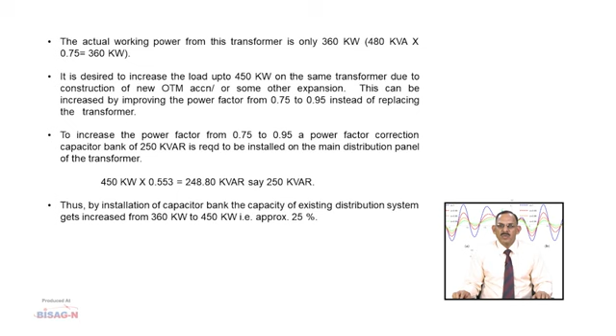Impact of power factor correction capacitors on improving voltage condition of distribution system. Low voltage resulting from excessive reactive current causes motors and other electrical gadgets to be sluggish and overheated. As power factor decreases, total line current increases, causing further voltage drop. Adding capacitors to the distribution system improves the system voltage, resulting in efficient performance and longer life of all connected electrical gadgets.